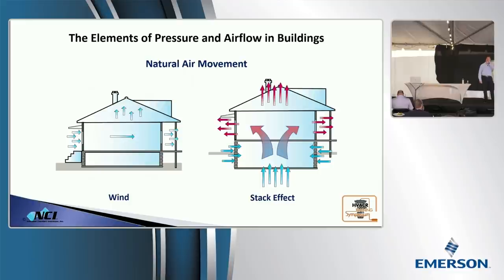What do you think happened when I went down and talked to the carpentry guys? I said, you care if we close those doors for a couple of seconds? What do you think happened to the inducers going backwards? You think they kept on going? They stopped. We stopped the path because air takes the path of least resistance. Those 20 by 20 doors were the path of least resistance. So here's what was happening.